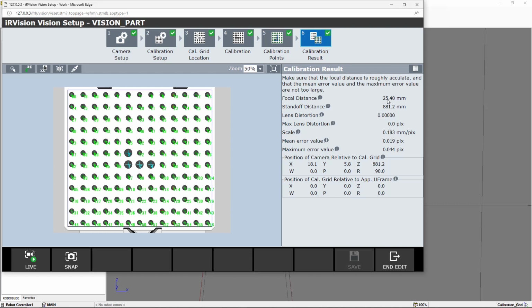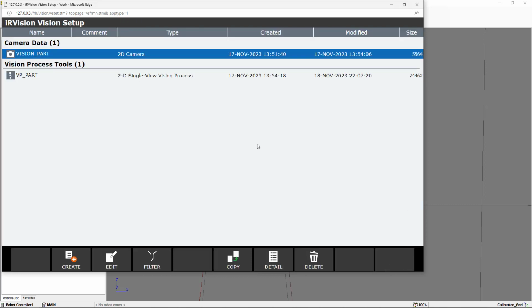The focal distance, you can see, is 25.4 instead of the 25 millimeters that I have in the properties for the camera. And you're going to see that the position of the camera relative to the calibration grid has this offset, and the position of the calibration grid relative to the application user frame has a 0 offset. We're going to save, and with this we finished the camera calibration, and we can end the edit.